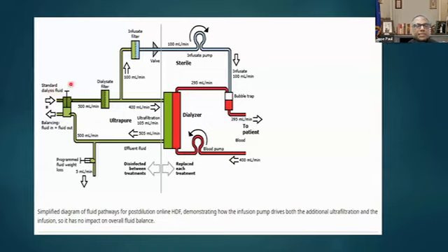So to conclude, this is a simplified diagram which is used in hemodiafiltration. The standard dialysis fluid is generated by the machine using the concentrate and the RO water. It runs through a balancing system, then through the first dialysate filter. It generates ultra pure water and it goes through the infusate filter. This filter can be either before the pump or after the pump.